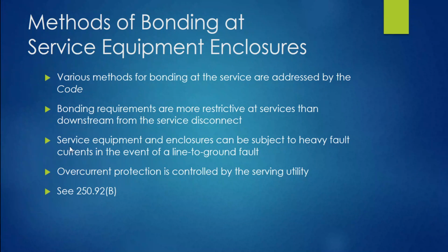All right, so the service equipment and enclosures can be subject to heavy fault current, obviously, because there's no overcurrent protection device that we're aware of. Okay, it might be on the primary side of the transformer, but there is a potential for a higher level of fault current, and so we need to make sure those connections stay solid and done properly. And again, the overcurrent protection is controlled by the service utility. And I am going to just remind you again that all of those connections on the service conductors on the line side that's coming from the utility, they only have overload protection based on whatever the overcurrent protective device in the breaker that it's feeding in the panel.